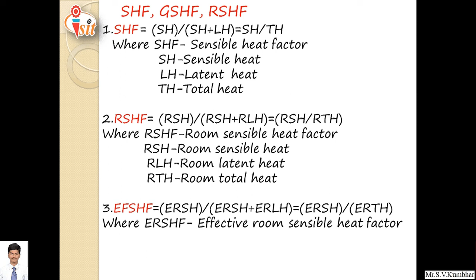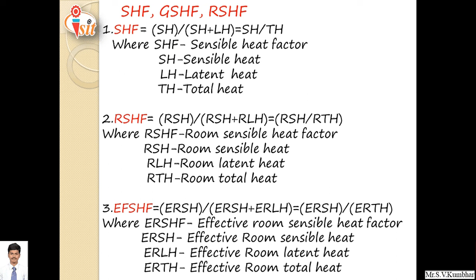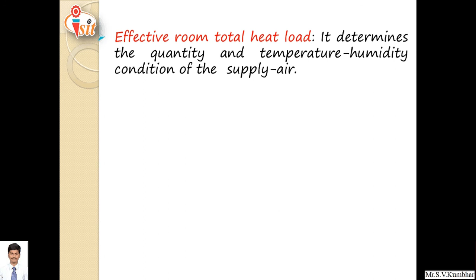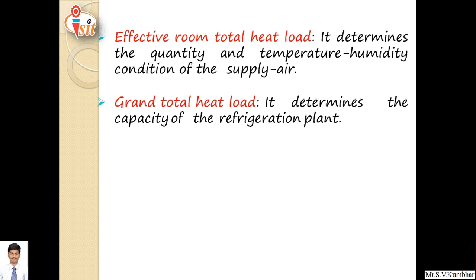Third important part, effective room sensible heat factor. Effective room sensible heat factor is the ratio of ERSH, meaning effective room sensible heat, to effective room total heat, and effective room total heat is the summation of effective room sensible heat plus effective room latent heat. Effective room total load determines the quantity and temperature and humidity condition of supply air. Grand total heat load determines the capacity of the refrigeration plant.